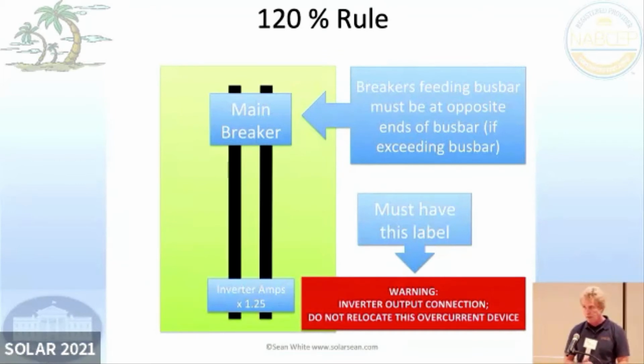And it used to be the 120% rule was based on the solar breaker size. And then I think it was in the 2014 NEC, they changed it to, instead of saying the solar breaker size, because sometimes people would put one microinverter, which is like about 1 amp, on a 20 amp breaker. And so all of a sudden you're dinged by 20 amps for using 1 amp. Now it's based on 125% of inverter current, which is how you size overcurrent protection devices. We're going to say that if we put things at the opposite ends of the bus bar, the main breaker plus 125% of the inverter current cannot exceed 120% of the bus bar rating.